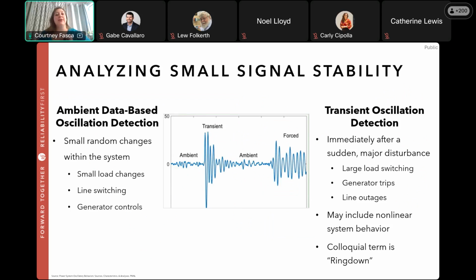So here we're going to cover system response types and their detection methods. You'll see the oscillation system response types broken out in that graph in the middle: ambient, transient, and forced. An ambient response is the response of the system to small random changes. So this would be load, line switching, or generator controls. And as you can see on the left and the middle of the graph, they're small, the amplitudes are short.